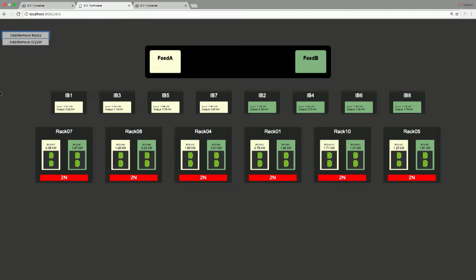So in this case, the math is as follows: you have 36 kW being fed from Feed A, 36 kW being fed from Feed B, and each rack is sized for 6 kW.